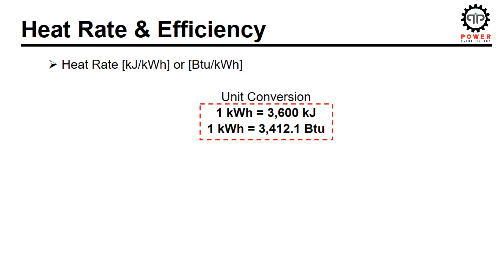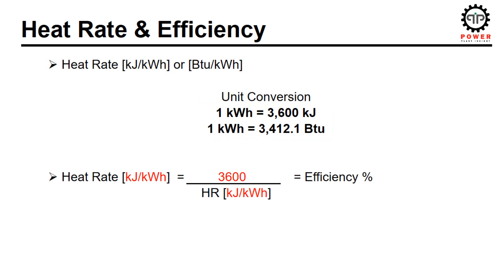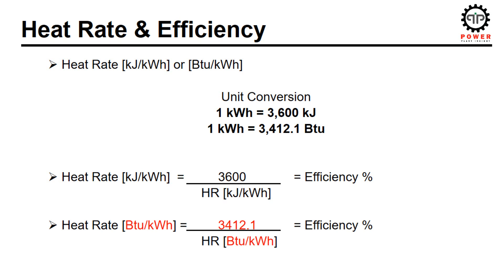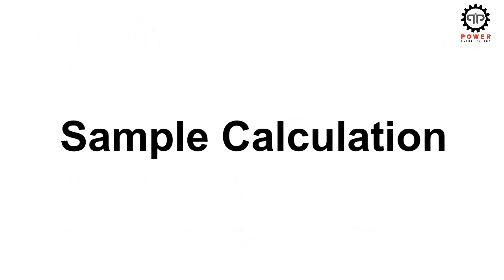One kilowatt-hour is equal to 3600 kJ, and in terms of BTUs it is 3412.1 BTUs. If the resultant value of heat rate is in SI units, we divide 3600 by the value of heat rate to get the efficiency numbers. If the heat rate is in BTU per kWh, then the value of 3412.1 will be used in the numerator.